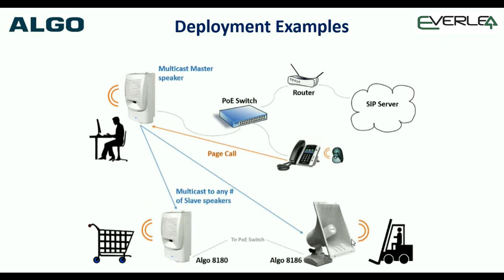In a multicast scenario: if we've got a SIP server in the cloud, we've got a router going through the PoE switch, a multicast master speaker receiving the page from a local call dialing the SIP number - it goes through the SIP server to the master and pages out to the various devices. The point is you can put the specific device you need for each area - for example, the 8186 in a warehouse area or open bullhorn area where it might be exposed to weather. Just horses for courses.